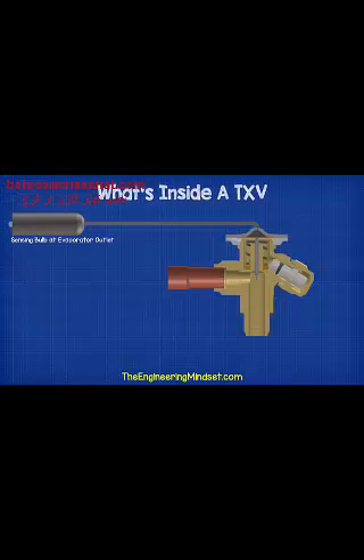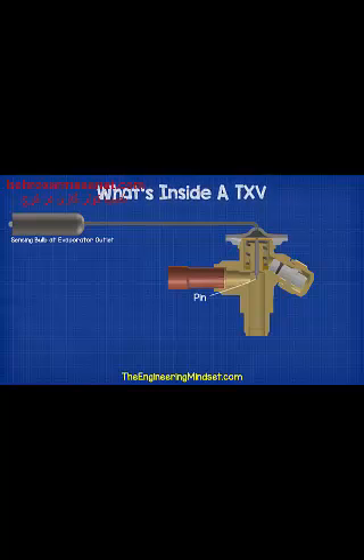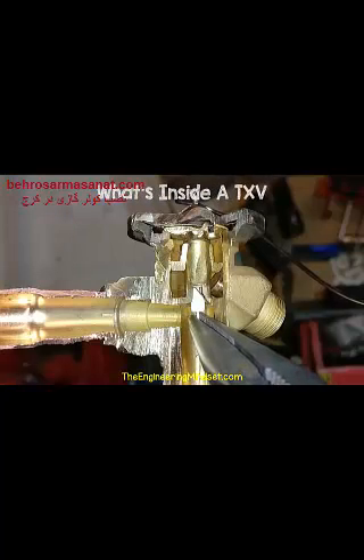So what's causing the change in pressure, temperature, phase and also controlling the flow of refrigerant? Well, we can see this small pin here. This is connected to the diaphragm up in the power head. The diaphragm is a thin sheet of flexible metal. As the diaphragm moves up and down, it causes the pin to move up and down also.